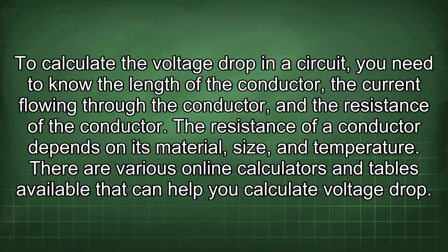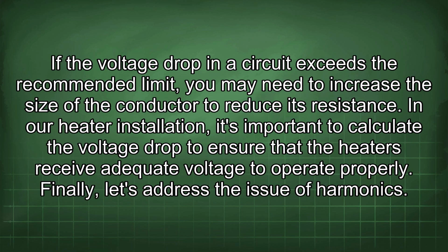The resistance of a conductor depends on its material, size, and temperature. There are various online calculators and tables available that can help you calculate voltage drop. If the voltage drop in a circuit exceeds the recommended limit, you may need to increase the size of the conductor to reduce its resistance. In our heater installation, it's important to calculate the voltage drop to ensure that the heaters receive adequate voltage to operate properly.